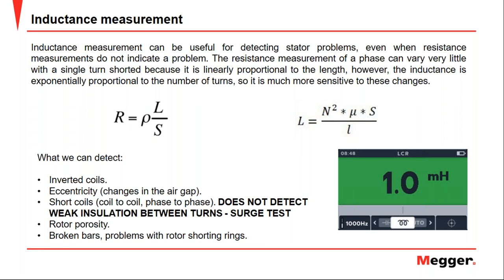First of all, we can detect inverted coils. Second, eccentricity, a change in the air gap, because of the rotor electromagnetic influence on the stator. And here is a very important aspect: short coils, between coils or between phases. But I have a very important thing to say here. The inductance test does not detect weak insulation between turns. That can only be done through the surge test. So we can detect shorts with the inductance test, but if we want to be predictive and be ahead of the failure, we have to do the surge test. Also, we can see rotor porosity or broken bars.